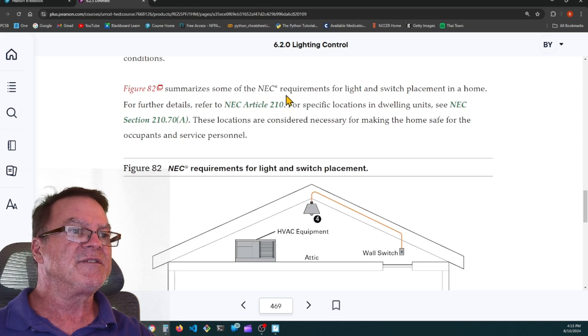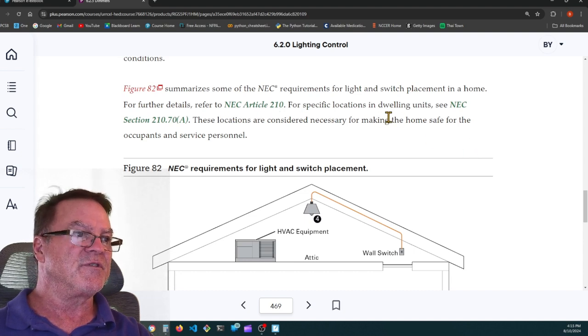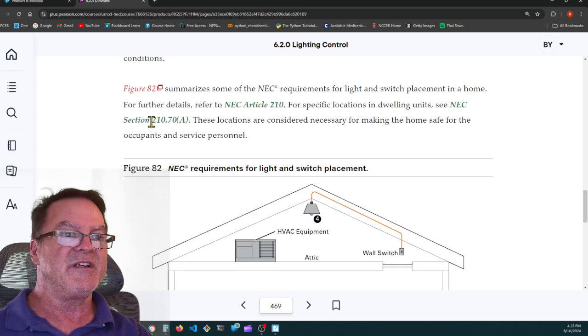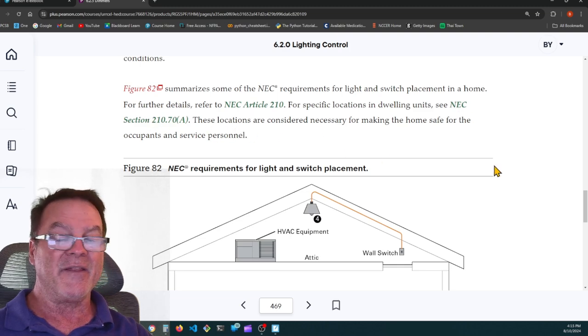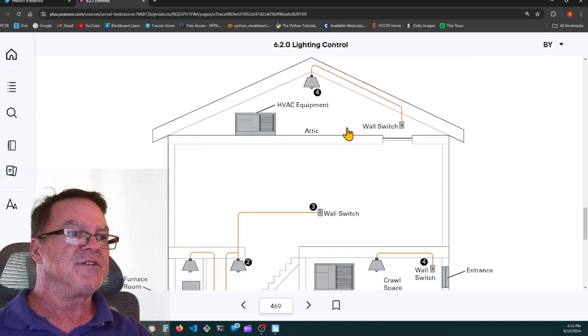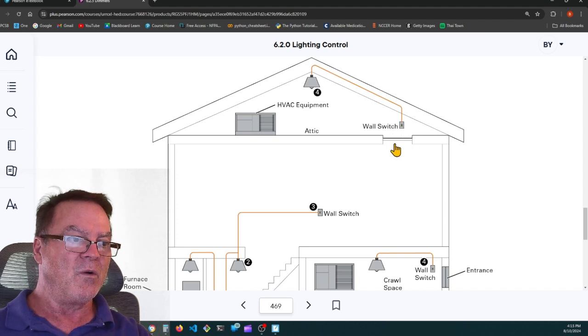Figure 82 summarizes some of the NEC requirements for light and switch placement in a home. For further details, refer to NEC Article 210. For specific locations and dwelling units, see Section 210.70(A). That's what we were just reading. So here, you have HVAC equipment in the attic. You have to have a light illuminating that equipment, and the switch has to be at the scuttle hole.